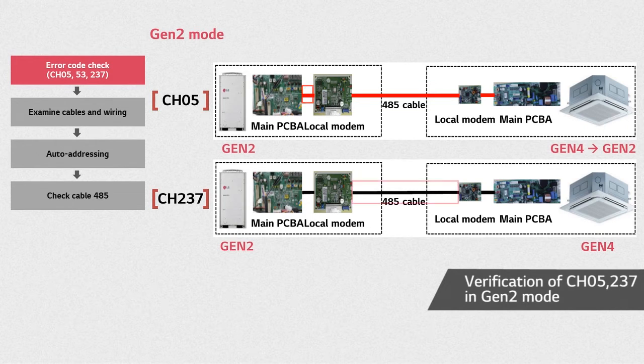Let's discuss CH237 in Gen2 mode of the ODU. Sometimes, when the IDU cannot communicate with the ODU since power reset time, the IDU remains in Gen4 mode even though the ODU is set to Gen2. In this case, CH237 will occur.